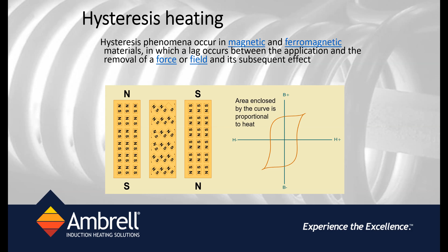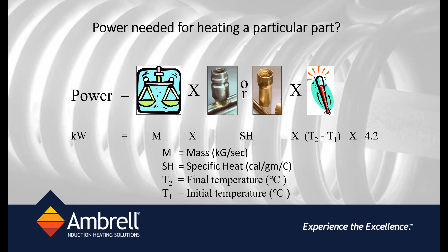How does one determine how much power is needed to heat a particular part? A simple mass and thermal equation is used, where if you know the rate of metal that needs to be heated, the specific makeup of the metal, whether it's steel, brass, or aluminum, and the rise in temperature required, all are needed to determine how much energy is needed to heat the metal part to a certain temperature. Mind you, this is not the size of the power supply needed, because you also have to account for conduction, convection, and radiation type losses from the part being heated to get a good understanding of the total energy picture for this process. Once you know all that, you can easily determine what induction power supply is needed.